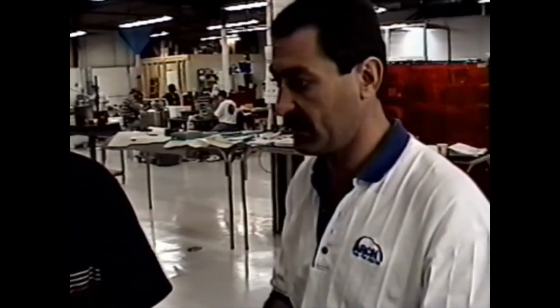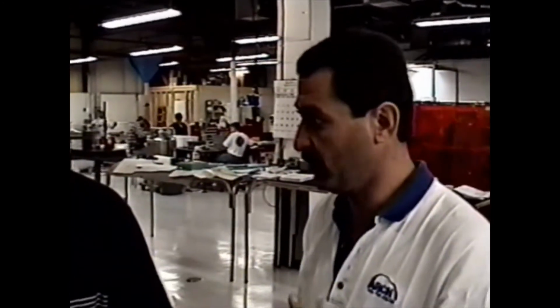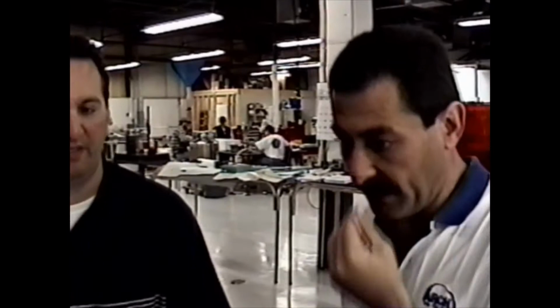Okay. Calibrate the transducer. You do it in 3 stages, basically. If this one was in a semi-clean room or outside, I will tell you what the 3rd stage is. If it's not, it only has 2 stages. Okay. The first thing is you apply vacuum. You open V29. No, I'm going to tell you. I'm going to go outside and smoke a cigarette and come back. I expect it to be done.